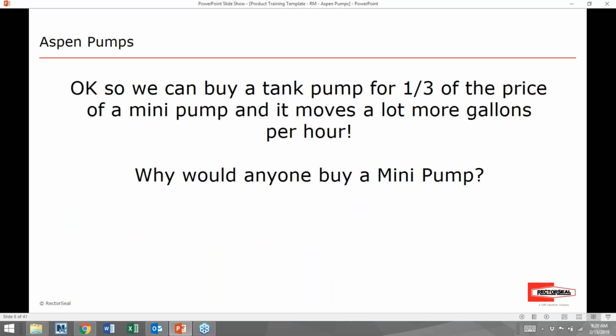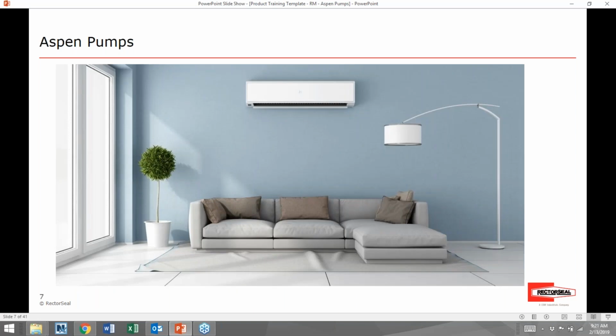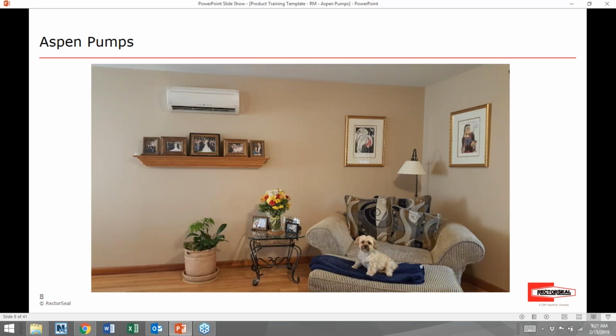So that would beg the question, if we can buy a tank pump for a third of the price and it moves a lot more water, why would anyone ever buy a mini pump? Well, because that unit right there above the couch has a pump inside of it, and it's a very clean and sleek look, and people will accept that. And there over the mantle, same thing. There's a pump in that that's pumping away the condensate being produced, and no one's the wiser.